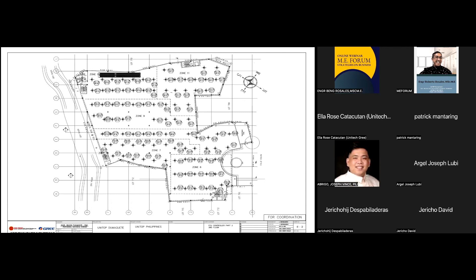Individually, I divided it into many zones, I think 16 in total. Each zone is home run to the controller, since that's where I placed our control panel. If you look at this, different zones correspond to different numbers of FCUs. By the way, the max number of FCUs in a single controller is 16, so they're divided among 16 FCUs.